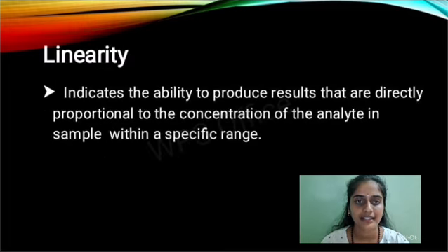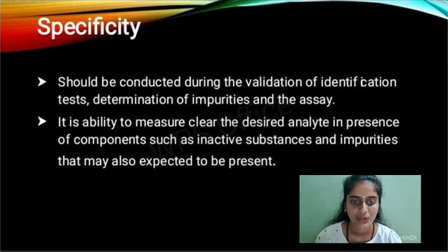Next, move on to linearity. Linearity indicates the ability to produce results that are directly proportional to the concentration of the sample within a specific range. This means that as the analyte concentration increases, the measured signal should also increase in a proportional, linear manner.